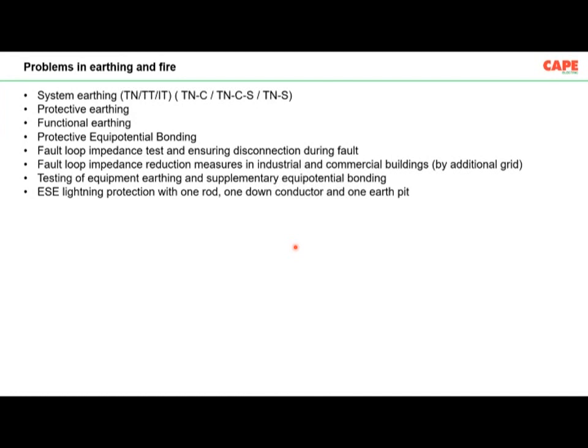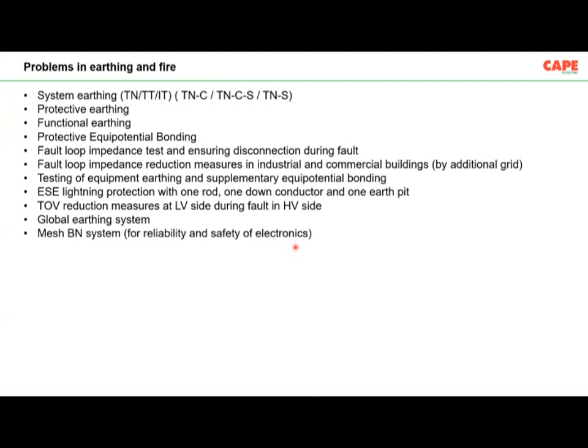Early streamer emission lightning protection with one rod, one down conductor, one earthing is followed. Temporary overvoltage reduction in the low voltage side of a transformer during a fault in HV side is generally not carried out. Global earthing systems are not followed. Mesh bonding systems are not followed. Actually, a good earthing means all the above. So a good earthing means you have to have a very strong, a good system earthing, protective earthing, functional earthing, protective equipotential bonding, fault loop impedance and reduction measures with a tested system, TOV reductions, temporary overvoltage reductions due to a high voltage fault, nothing should fail on the LT side, mesh bonding network and so on. This is what is about earthing in a modern building.